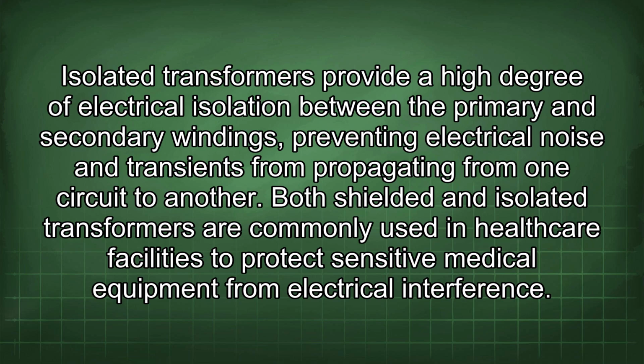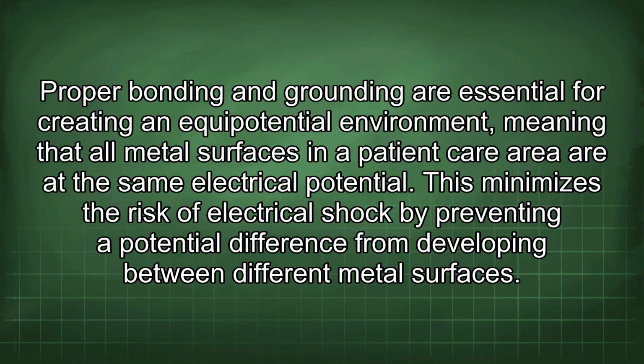Isolated transformers provide a high degree of electrical isolation between the primary and secondary windings, preventing electrical noise and transients from propagating from one circuit to another. Both shielded and isolated transformers are commonly used in healthcare facilities to protect sensitive medical equipment from electrical interference. Proper bonding and grounding are essential for creating an equipotential environment, meaning that all metal surfaces in a patient care area are at the same electrical potential. This minimizes the risk of electrical shock by preventing a potential difference from developing between different metal surfaces.